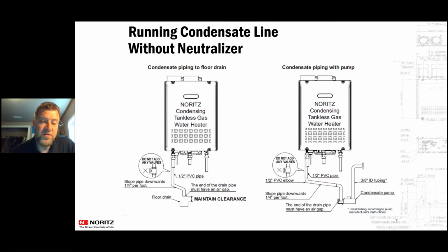On the bottom of that unit, it is going to have a 1/2-inch MIP adapter coming out of that. You can run 1/2-inch PVC pipe. You can run CPVC. You could run PEX. You could run whatever you're coming off of that. We just look at it as make sure that you're running everything on that condensate line in plastic. Don't run any metals on that, because condensation is very acidic and it will eat away. If you put a brass fitting on the bottom of that and you're running it out, it'll eat away that brass fitting after a while.